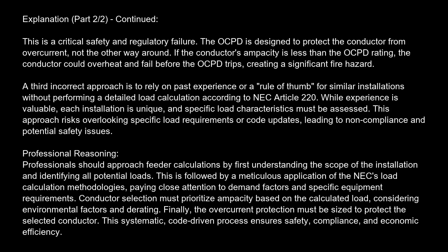A third incorrect approach is to rely on past experience or a rule of thumb for similar installations without performing a detailed load calculation, according to NEC Article 220. While experience is valuable, each installation is unique, and specific load characteristics must be assessed. This approach risks overlooking specific load requirements or code updates, leading to non-compliance and potential safety issues.